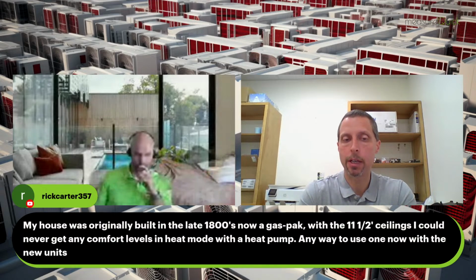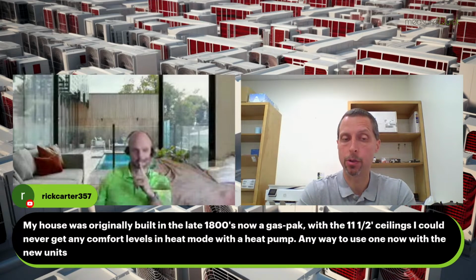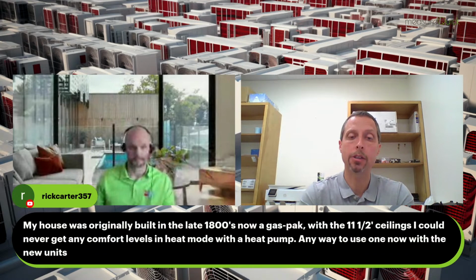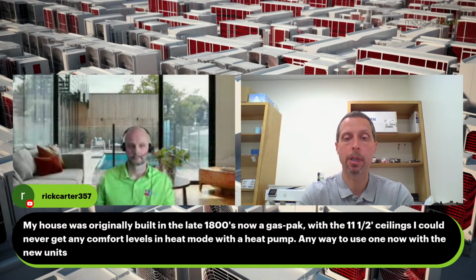And what it's going to boil down to, and I'm really oversimplifying this for the sake of time, is there's a set of metrics, right? Sizing limitations or sizing factors using variable capacity equipment following this new advanced cold climate heat pump sizing method. We're going to look at not only max capacity limits, but also minimum capacity limits, to make sure the unit's going to perform well and stay loaded up, so we avoid some of those compressor failure issues and dehumidification issues and such.